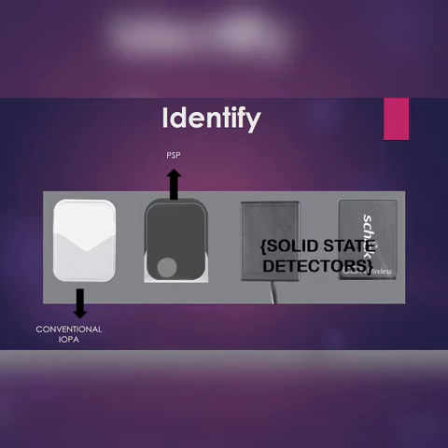So as we all know, the solid state detectors include the CCD, CMOS and FPD. FPD is mostly used for extraoral imaging purposes only. CCD and CMOS don't differ structurally, but the way in which the data is analyzed makes the difference. So the first one is an example of a wired CCD detector, and the last one is a wireless CMOS detector.